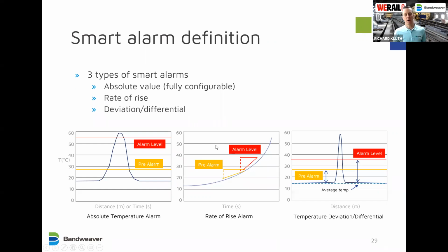So what do we mean by smart alarms? Well, broadly speaking, there's 3 types of smart alarms: the absolute value, rate of rise, and deviation or differential alarm. So absolute value is similar to conventional point sensor alarms in that if you exceed a value, the alarm goes if you go over a certain temperature. However, this is fully software configurable, so you can set the level at whatever you want, and you can set multiple levels, so you can have pre-alarms. So it gives you a lot more flexibility.